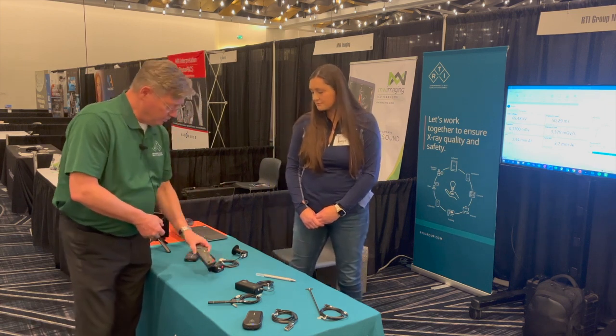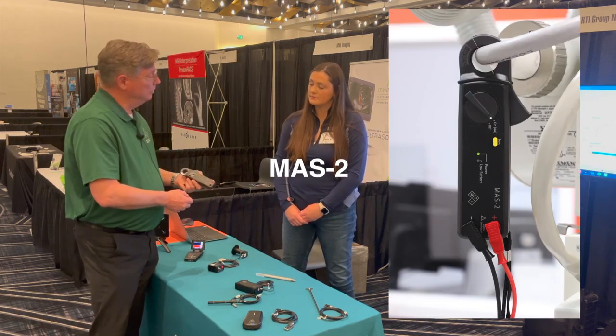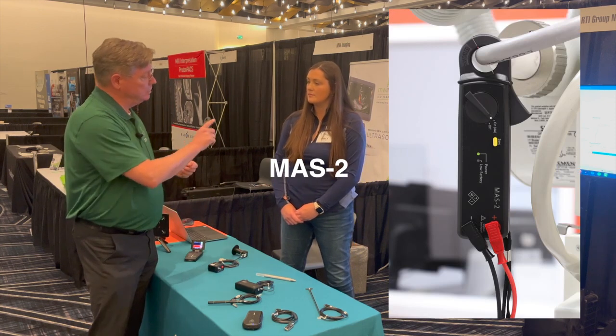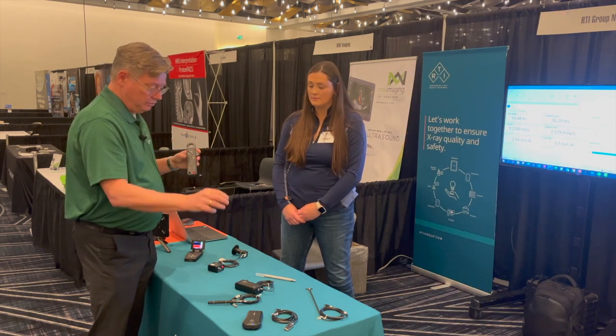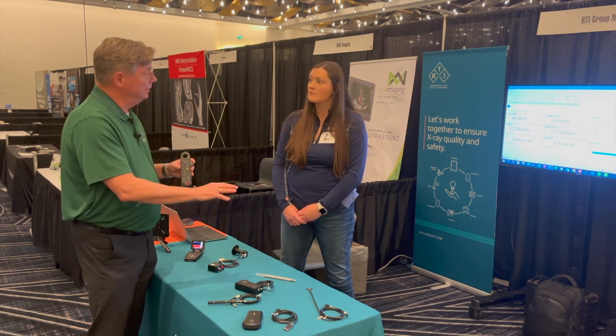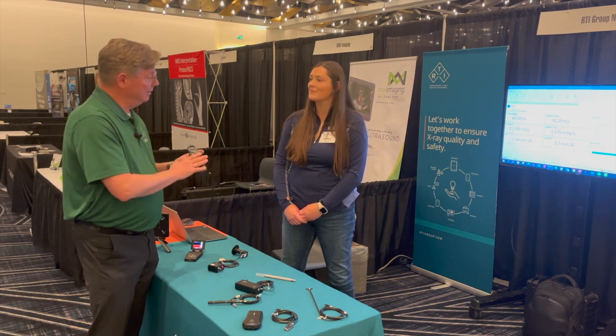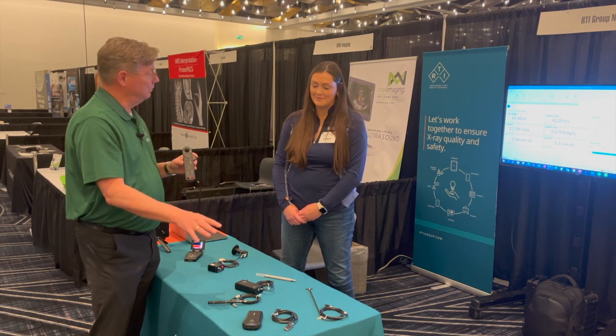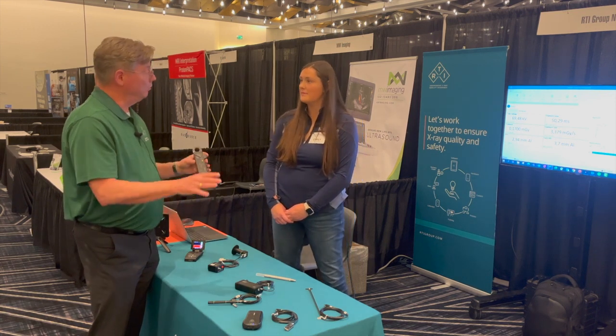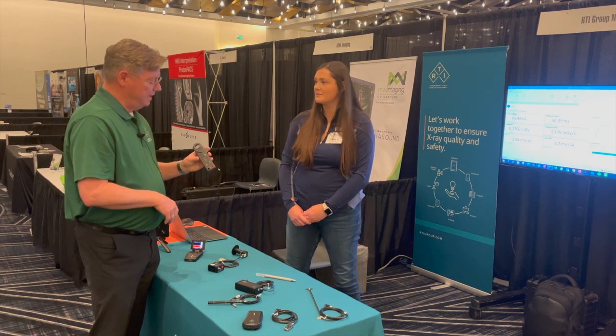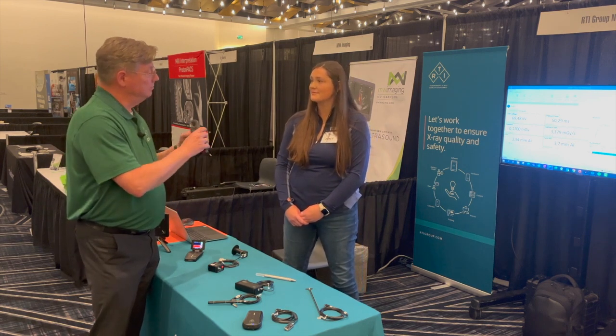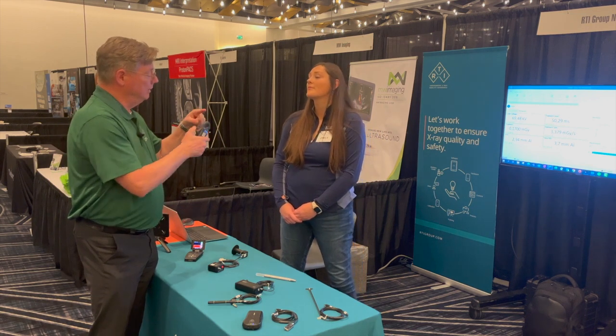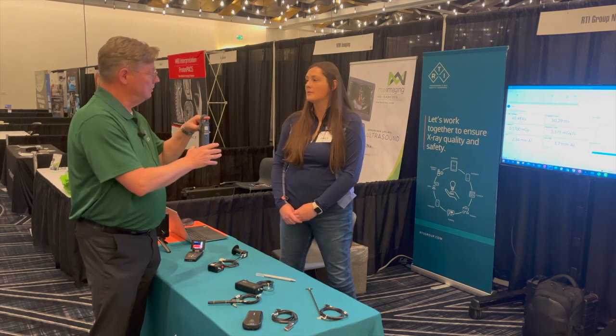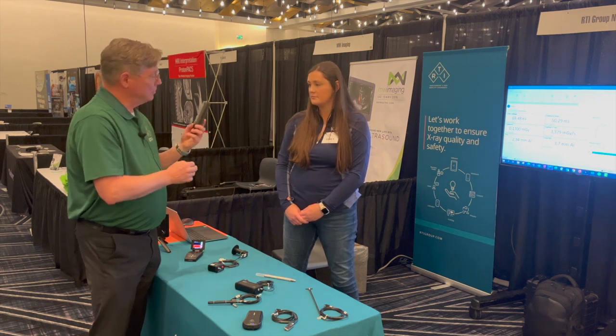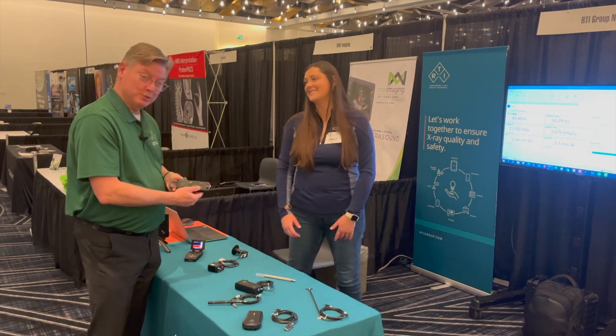Yes. So what we also offer is a MAS 2, which is a clamp-on version of doing it. So it actually clamps on to the high tension cable by the tube. We connect the wire here to the Piranha, put the Piranha in the beam. So in the one exposure, you just get the MA, MS, KV, dose, total filtration, and HVL, of course. Okay. All in one shot, superimposed. Makes sense. Yeah. And the most difficult thing when you're using this one is to attach it the right way. This way or this way around. So that's the most difficult trick or the difficulty to overcome with the MAS 2 probe.